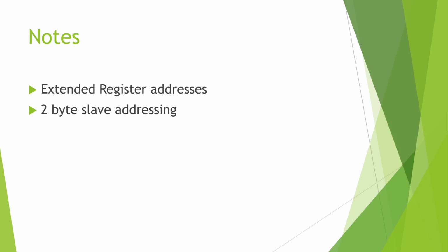Some software will limit you to only 49,999. Some will allow you to extend into that. It's something you need to be careful of. As much as Modbus is open source and everybody should be able to use it and it should all just work, well, not everything is defined. To me, these registers exist, right? We're using the bytes for them, so we might as well allow access to them. Why are we using those extra bits for information that we're not actually using? Might as well use them, as long as the device has space for it.